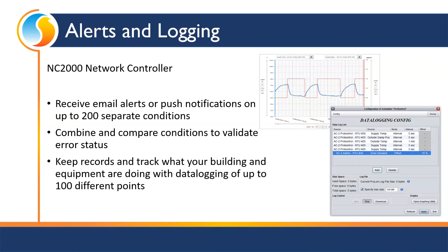We can also keep records. There's a slot for an SD card on here where you can do data logging. You can say, I want you to watch this sensor, and every 5 minutes make note of the temperature. Back to surgical suites, we have several medical facilities and a few hospitals using this data logging for their state records, to prove they're keeping their humidity and temperature in line with state requirements. It provides their records, and it comes out in a nice Excel CSV file that they can store easily.